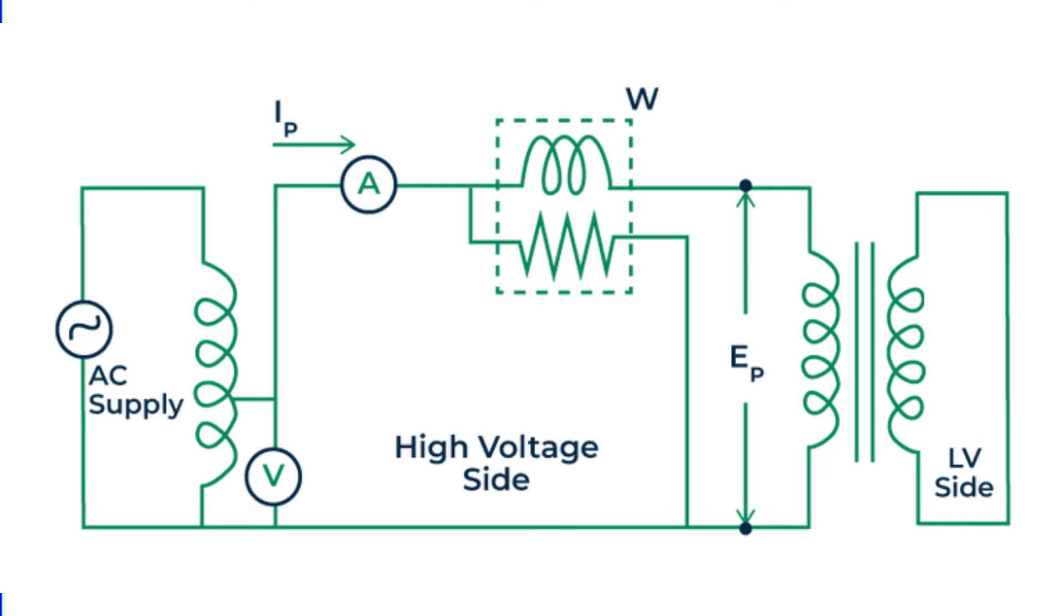So when we talk about percentage impedance, you can think of it this way. It's the percentage voltage of the rated voltage that's required to circulate the rated current flow through one transformer winding when the other winding is short-circuited at the rated tap position of the transformer.